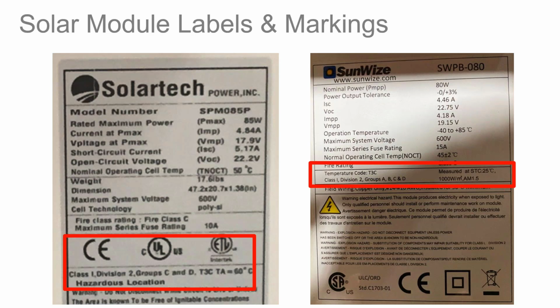So just as an example on the left, for the SolarTech Power SPM 085P, that solar module is actually only certified to group C and D. And they have other modules that are only certified to group C and D, whereas other modules of theirs, as well as all the SunWize C1D2 solar modules, are certified to groups A, B, C, D. So it's a small detail and note to be mindful of, depending on what exact group zone you're actually going to be installing these in.